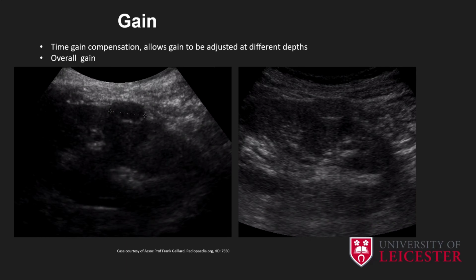Overall gain is an increase in amplitude of the return signal expressed on the screen as brightness. Turning up the gain will make the whole image brighter, and this can allow for better visualization, as you can see with this kidney. However, if you turn it up too bright, then it can white out areas of interest.